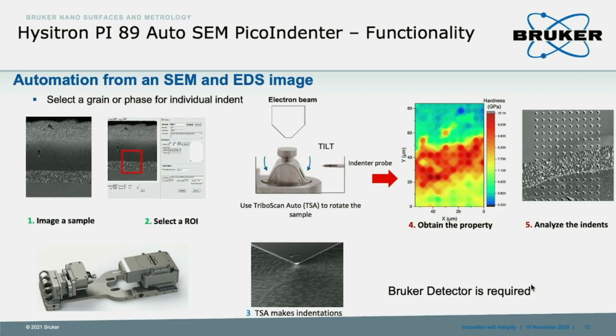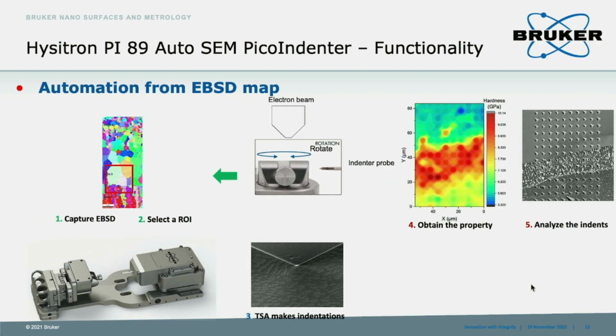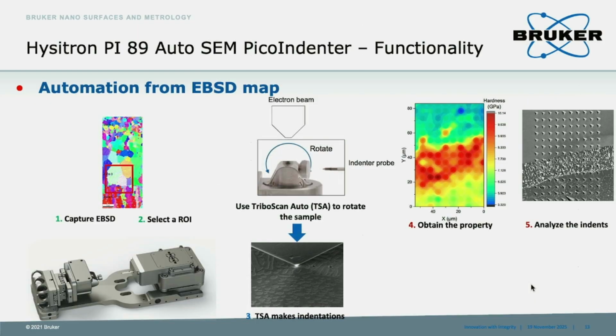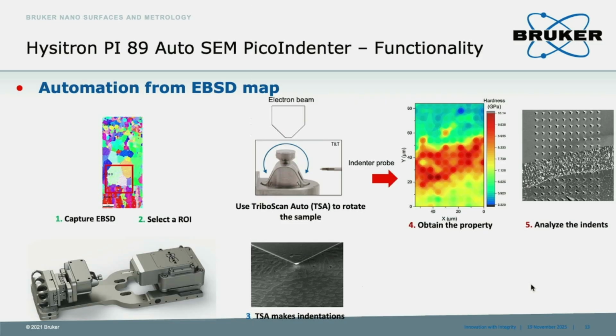Yeah, it's quite robust. EBSD is the same. For EBSD, we need to use the rotating stage: just turn 90 degrees and go back to the e-beam to see the post-test image. This is very powerful. If you capture the EBSD image first, then our system is calibrated with the SEM. Then you can get the post topography image, the mechanical properties mapping, and also EBSD in one chamber. You don't need to vent the SEM to take the sample out; you complete the testing here.